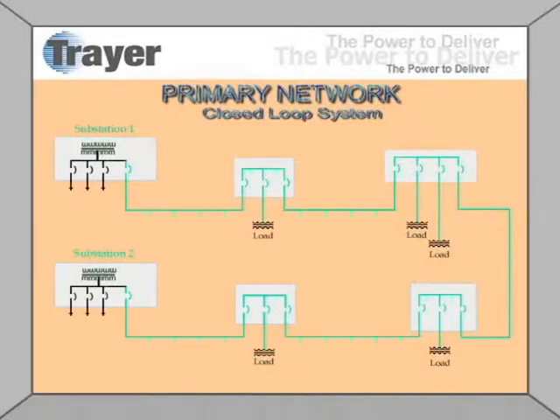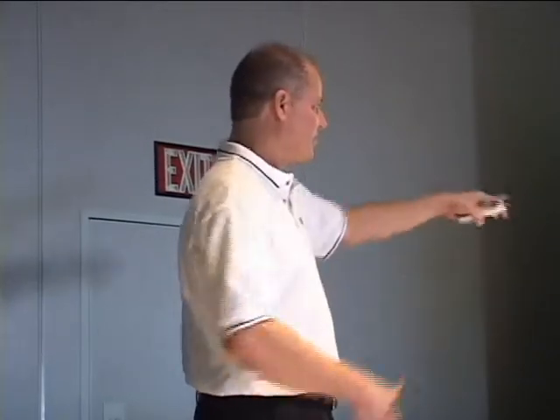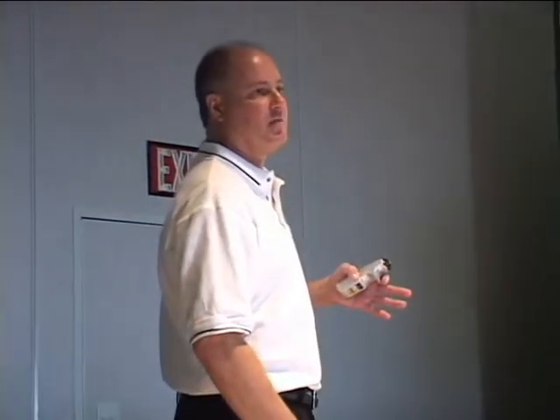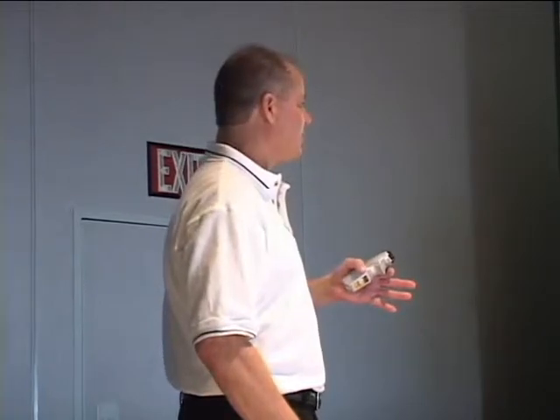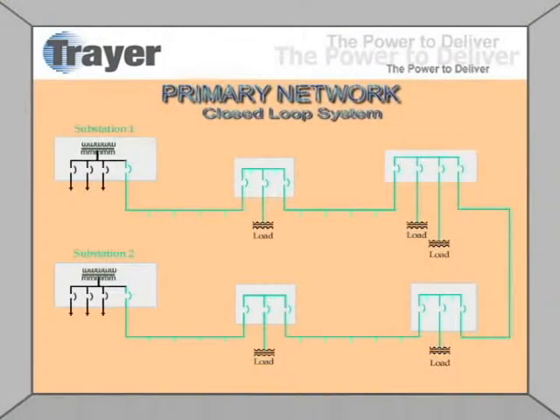Let's look at this load right here. He's not only being fed by this substation cable, but he's also getting power from this side as well. He has twice the copper, twice the cable going to his load. Half the system impedance feeding that load. And because of that, I call it a stiff system, such a stiff system that primary network users don't get complaints about voltage flicker.